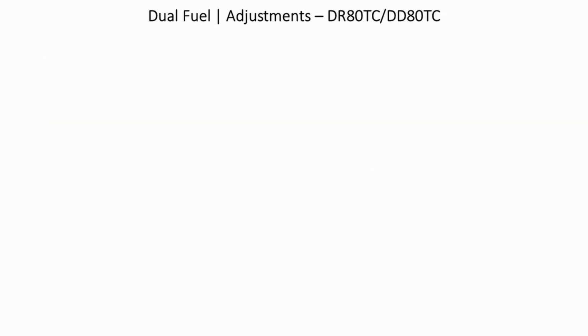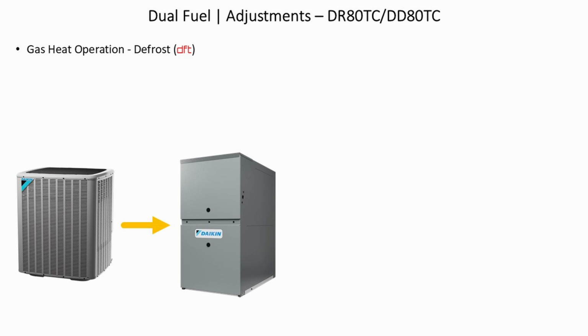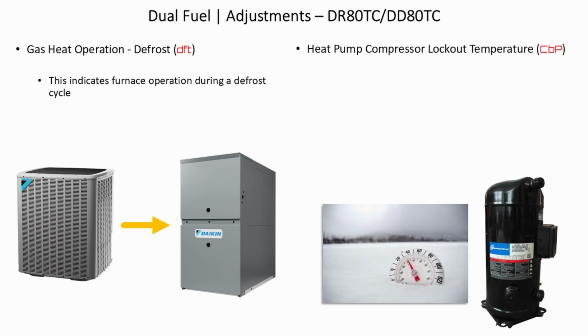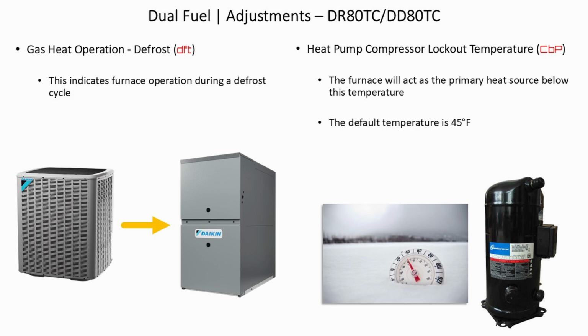Dual fuel adjustments. Gas heat operation, defrost, DFT, is displayed. This indicates the furnace operation during a defrost cycle. Heat pump compressor lockout temperature, CBP, is displayed. The furnace will act as a primary heat source below this temperature. The default temperature is 45 degrees Fahrenheit. The settings range from -15 degrees to 65 degrees Fahrenheit.